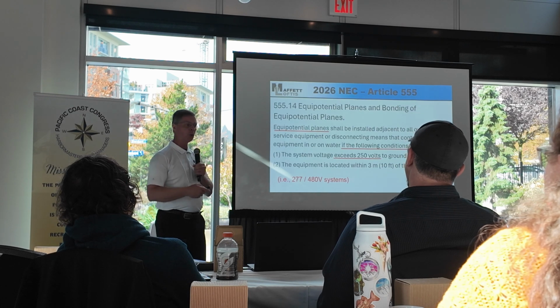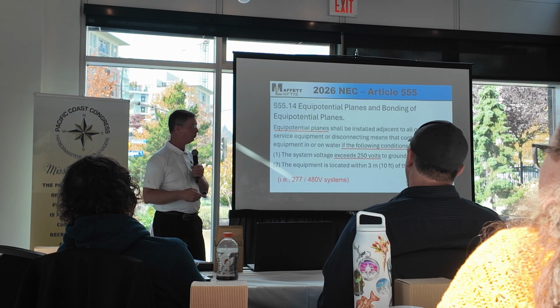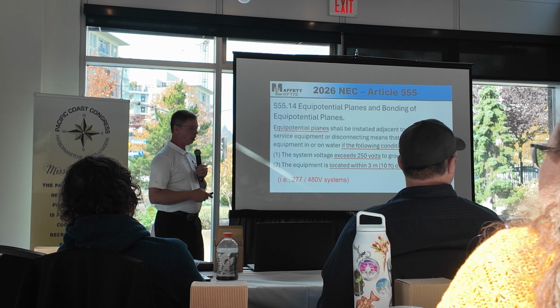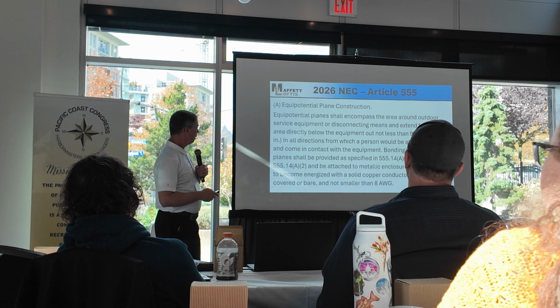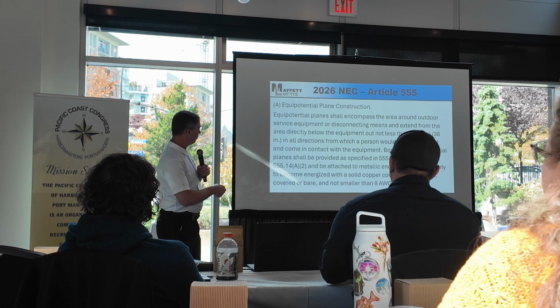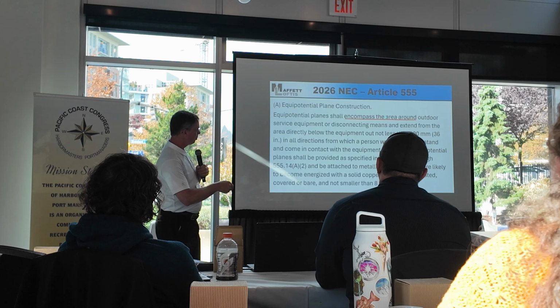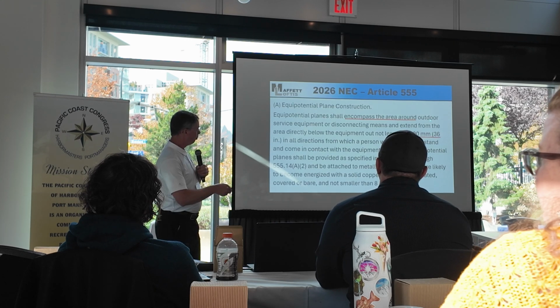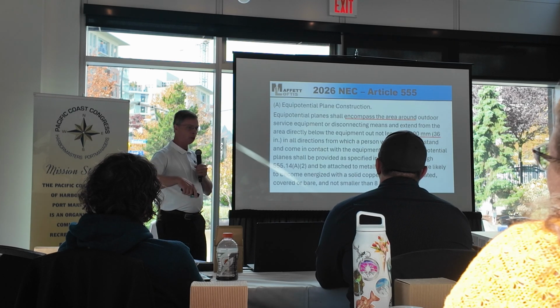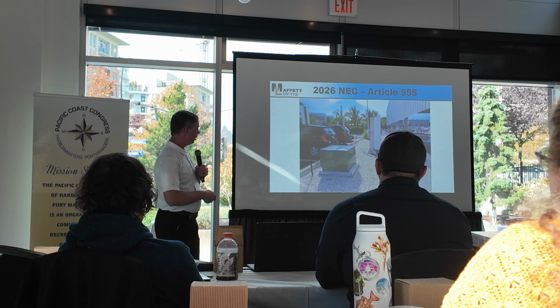And I'm going to go through this pretty quickly because it involves quite a bit of work, but just don't install it within 10 feet. But this is some of the stuff that you have to do. It encompasses the area around the outdoor equipment within 36 inches all the way around the equipment in all directions.